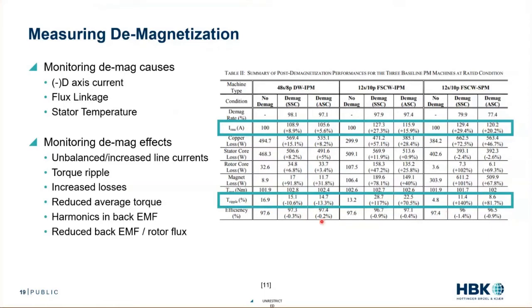Even if our efficiency changes are in the single percentage points, we can track the currents, we can track the torque ripples, we can track other things really early on so we can understand when this fault starts onsettig and how it increases with time. This shows us that for different winding configurations, we might need to monitor different things, but 5%, 10% — that's really easy to look for from a measurement perspective on direct measurements.